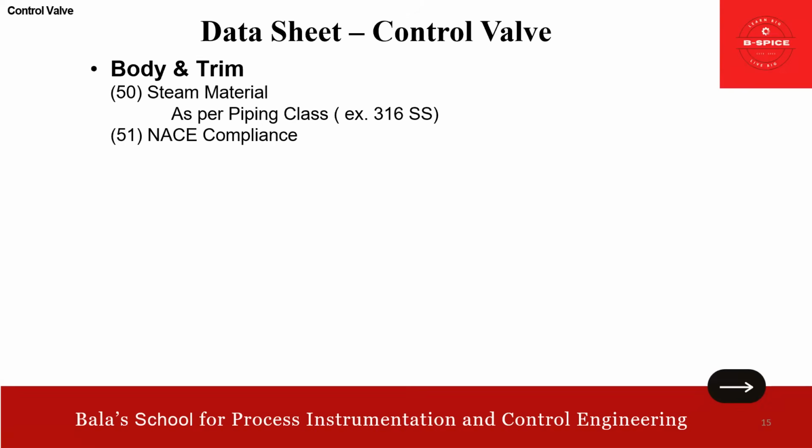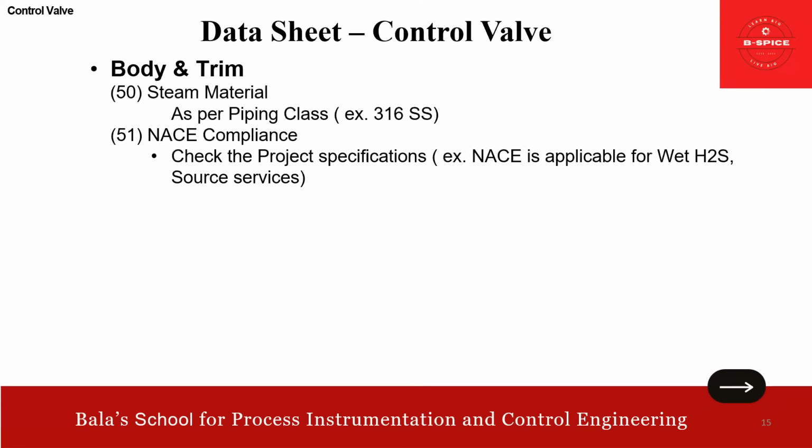So basically, this should comply with MR0103, which deals with materials resistant to sulfide stress cracking in corrosive petroleum refining environments. So that is what wet H2S and sour service is. If it is applicable, you put applicable.